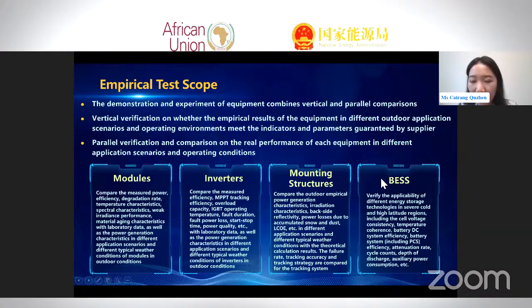And for the battery energy storage system, we verify the applicability of different energy storage technologies in severe cold and high latitude regions, including cell voltage consistency, temperature coherence, battery DC system efficiency, battery system efficiency, attenuation rate, cycle counts, depth of discharge, and auxiliary power consumption, etc.